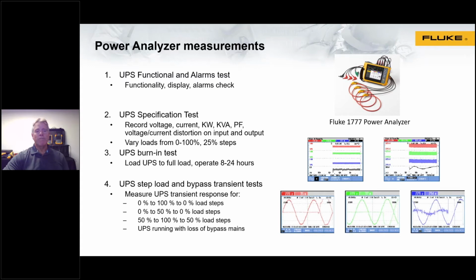Our next test, number 4, is called a step load and bypass transient test. So essentially what you're going to be doing here is showing the transient response of the UPS as you hit it with step loads. You'll be going in 25% steps, from 0 to 100 and back, 0 to 50 and back, 50 to 100 and back to 50, and then really observing that transient response. So is it responding properly?